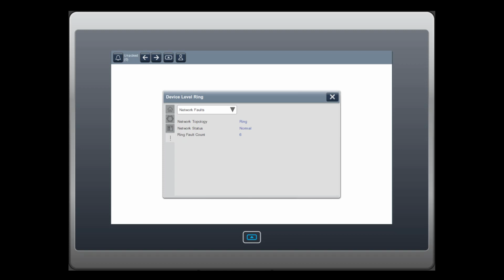Another common fault is the rapid fault or restore cycle fault. It occurs when there are more than 5 consecutive fault or recovery cycles detected in less than 30 seconds. This usually happens during network commissioning and indicates a severe hardware or cabling issue or misconfiguration that requires immediate attention. When this fault occurs, it is required to restore normal operations after the fault cause was determined and corrected.